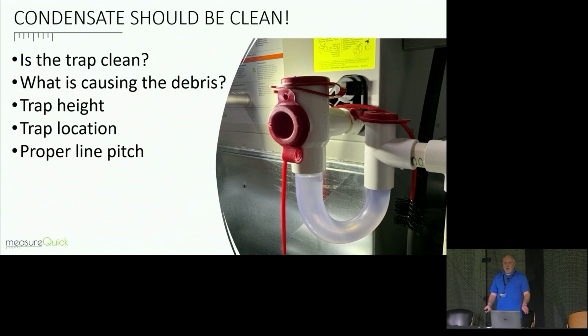No, but think about it for a minute. Where does that water come from? It's distilled water out of the air, right? If you think about what's happening there, in order to have biological growth, you have to have distilled water and what else? Something to eat, right? A food source in there. If you eliminate the food source by eliminating the dirt in there, you're going to eliminate your condensate trap cleanings.